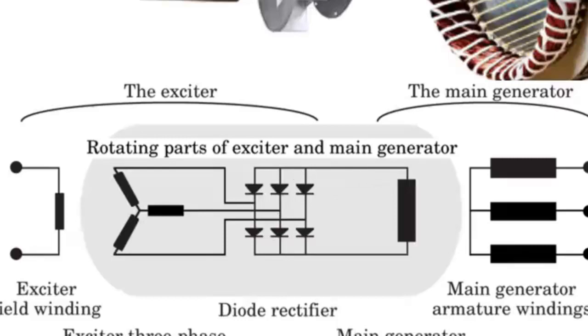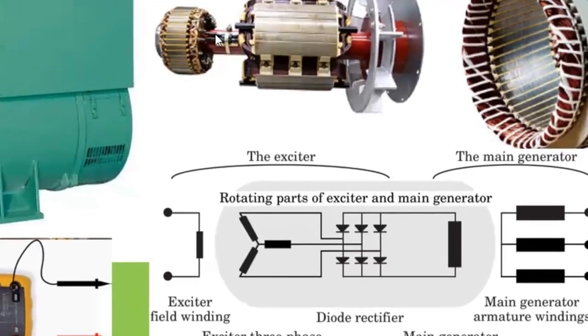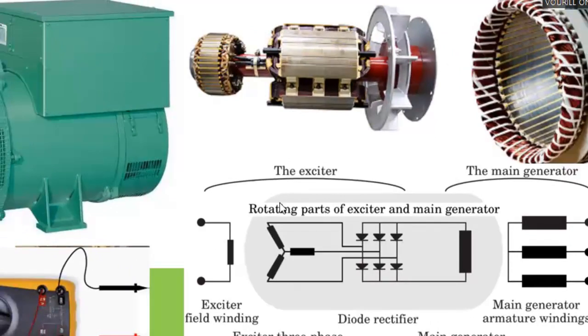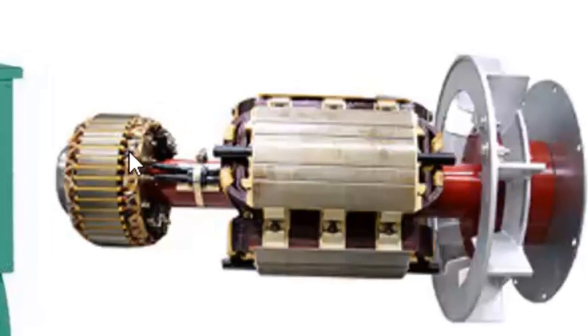This is the diode assembly, somewhere here. Then this is the exciter armature, which is this winding that you are seeing here, and this is the yoke. As you can see, the windings are also insulated from the yoke, so they don't have any business with ground. When it's shorting to ground, that means a problem is developing already.